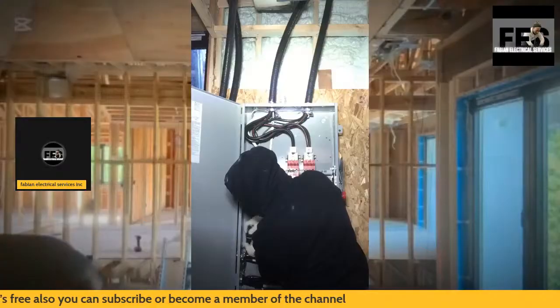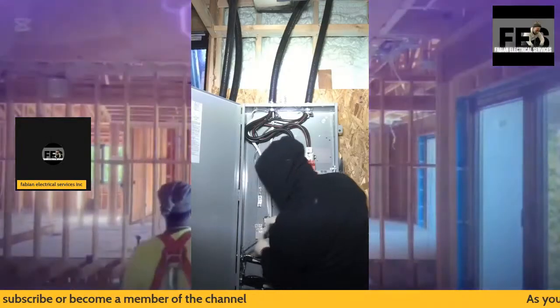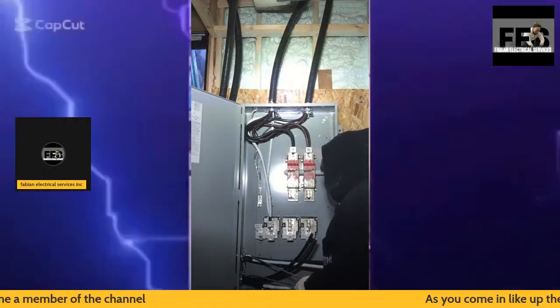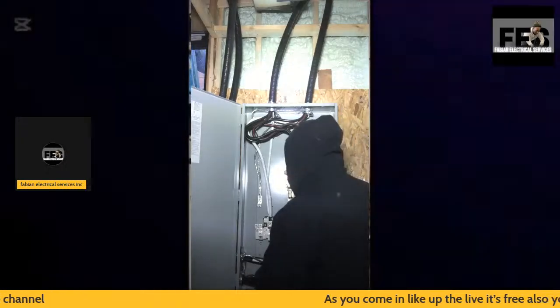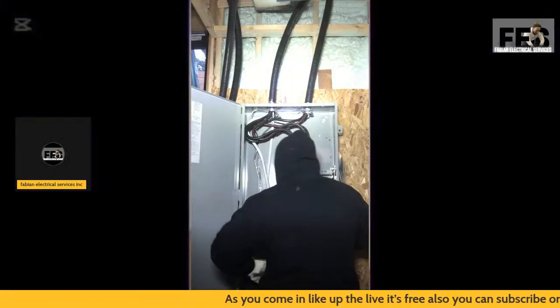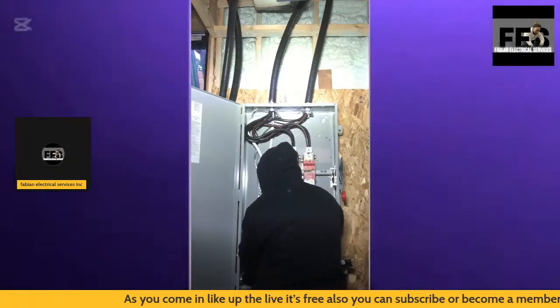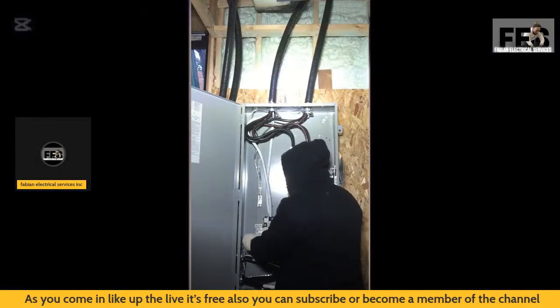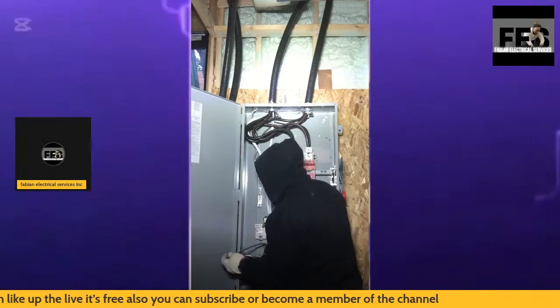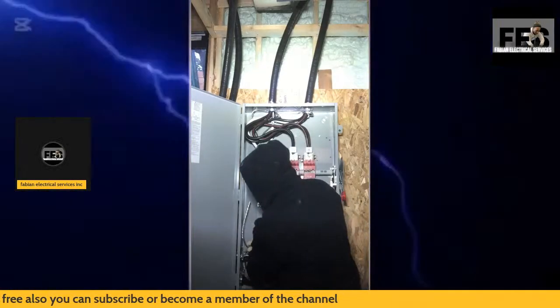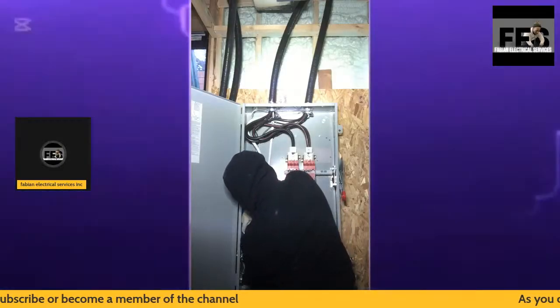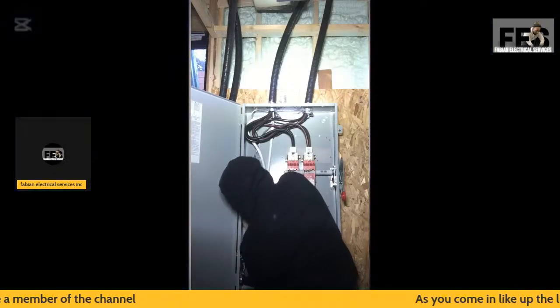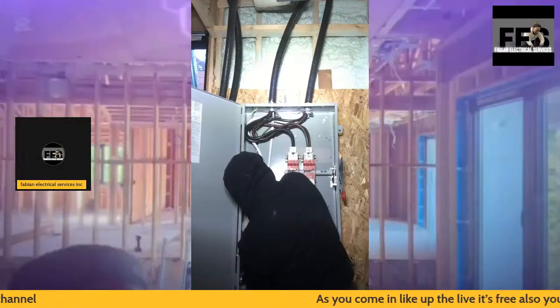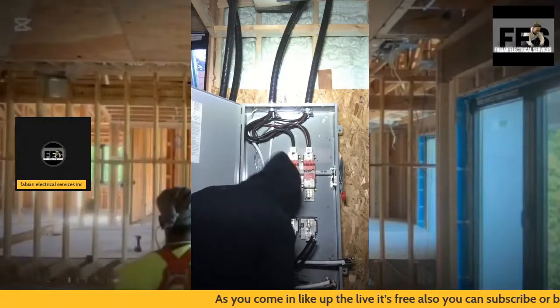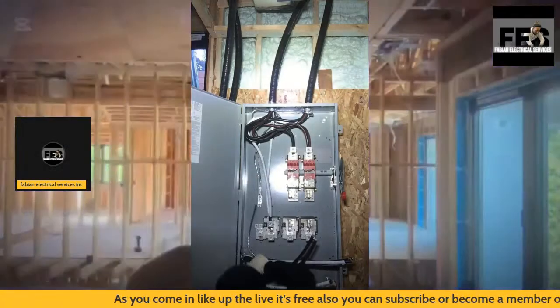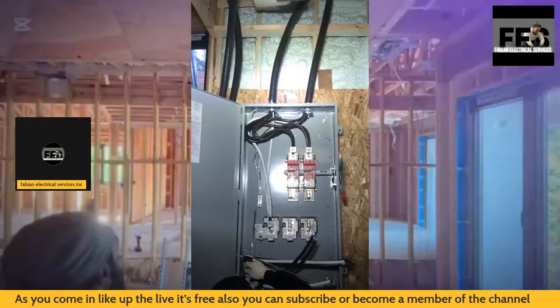You're also going to see me phasing the cable - that's another code compliance we have to follow. Everything here has to be up to code. We also have to have our CSA approved sticker on this 400 amp disconnect. Very important when it comes to the installation to have the sticker.